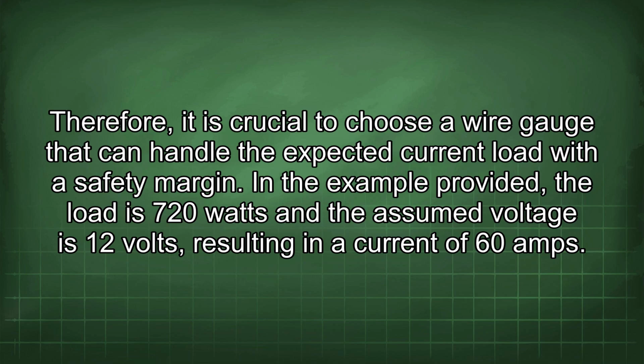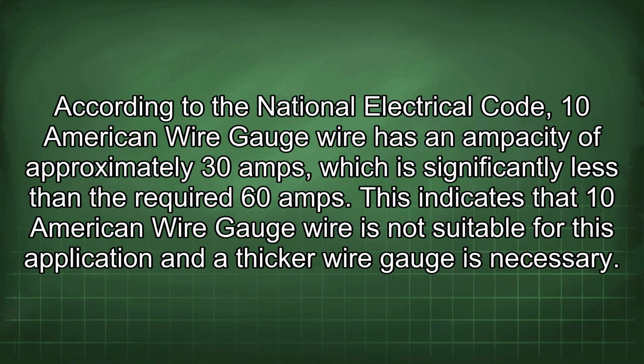In the example provided, the load is 720 watts and the assumed voltage is 12 volts, resulting in a current of 60 amps. According to the National Electrical Code, 10 American wire gauge wire has an ampacity of approximately 30 amps, which is significantly less than the required 60 amps.